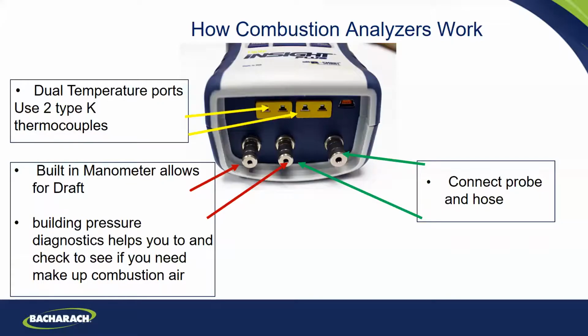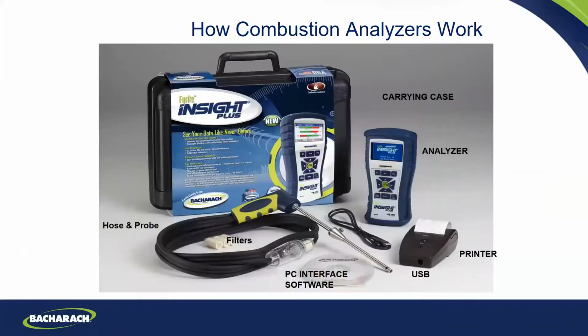Let's talk about how you would do a combustion test. Okay, so I'm going to come back to the screen. Like I said, you're going to plug in this hose and probe. Do not put the probe in a stack yet. You're going to turn on the on button here. The unit comes on. You pick your fuel, because every fuel has a different combustion efficiency formula. And it's going to run 30 to 60 seconds. Remember, do not put the probe in a stack yet.